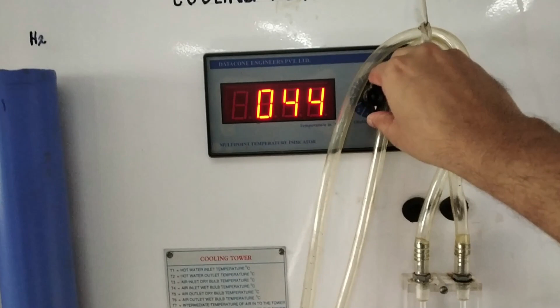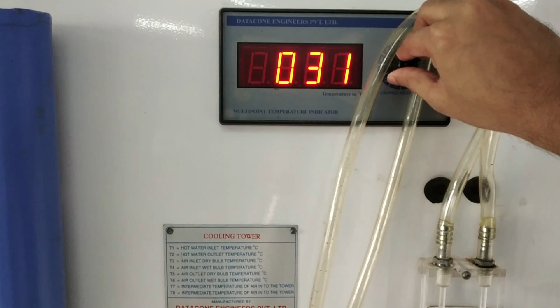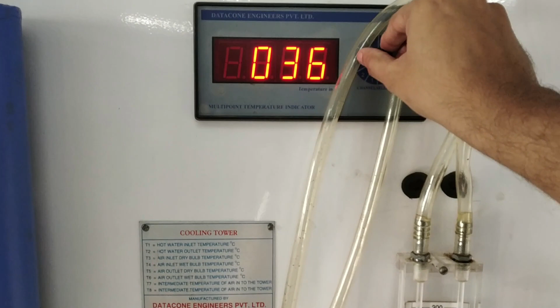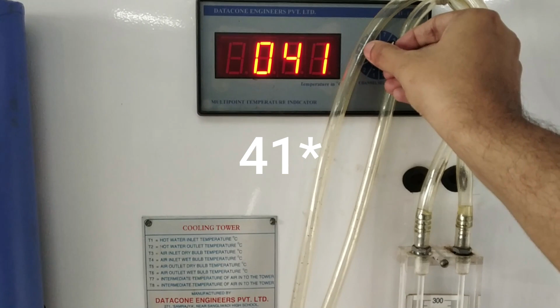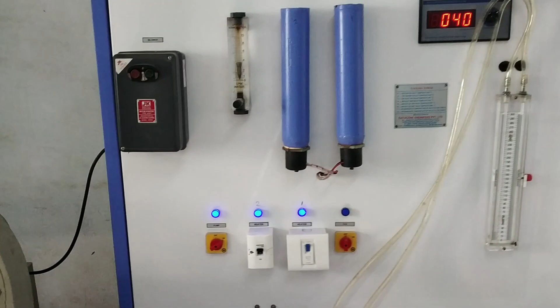Now we will check the temperature values. T1 is 44, T2 31, T3 31, T4 31, T5 36, T6 35, T7 31 and T8 40. Now after taking the readings, we will again increase the flow rate of air. We are going to keep the same flow rate of water. So we have again increased the flow rate of air. Now we will wait for 10 minutes and take the readings again.